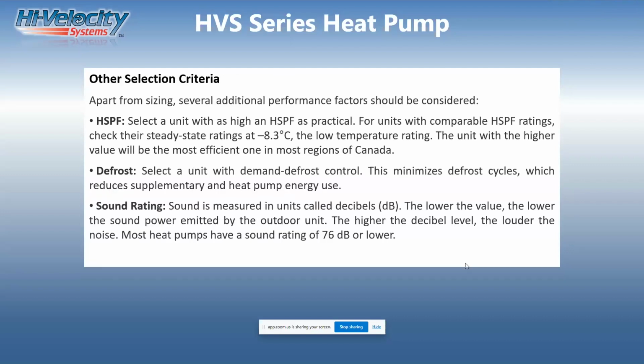So other criteria that's really important is sizing. Okay? Again, I don't think you can hear that enough about sizing. Select the unit with the highest HSPF as practical. Practical, that's a key word here. For units with comparable HSPF ratings, check their steady-state ratings at -8, the lower temperature rating. The unit with the higher value will be the most efficient one in your region. Defrost. Select a unit with demand defrost control. This minimizes defrost cycles, which reduces the supplementary and heat pump energy use.